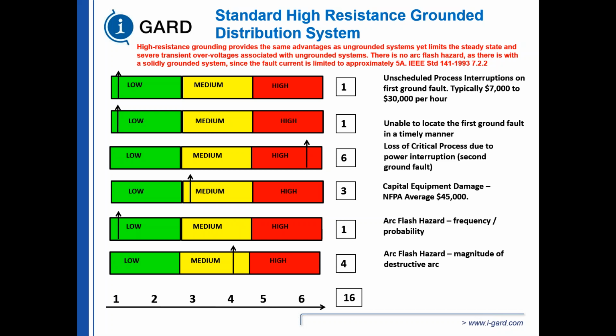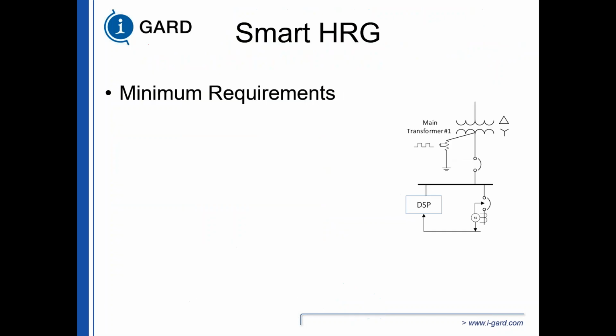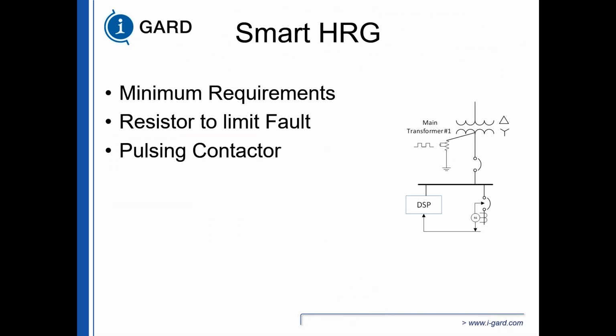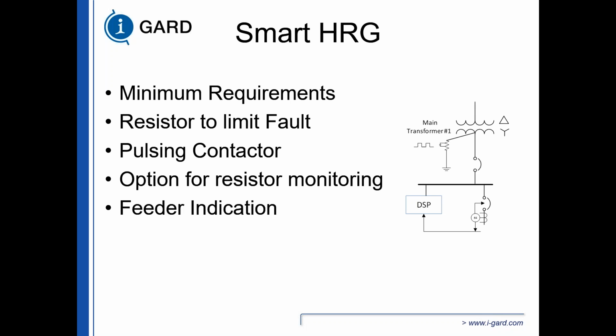So we end up with 16. Smart high resistance grounding. Minimum requirements. You need a resistor to limit the fault current. That's a given. You need a pulsing contactor because you want to locate where the presence of the fault is. You also need an option for resistor monitoring because, unlike the US, Canada has the need in the code of finding out if there's a fault in your resistor.